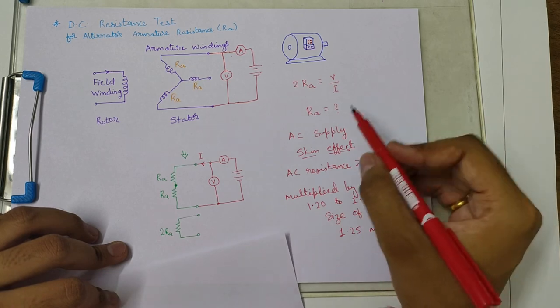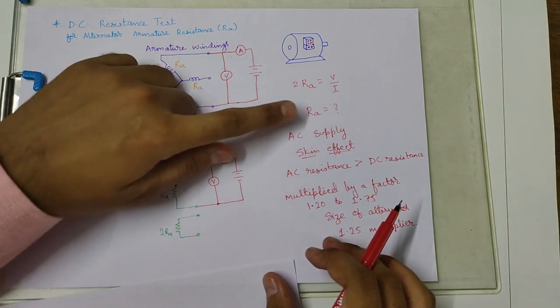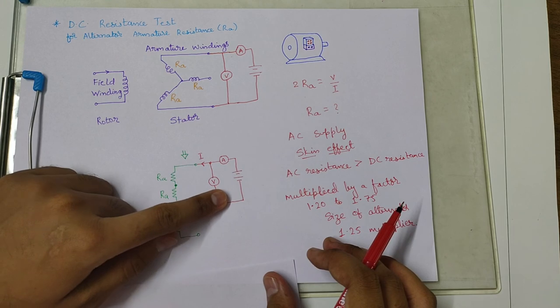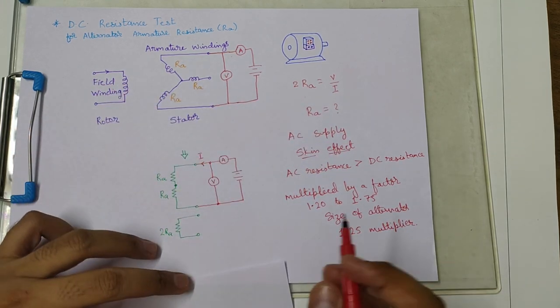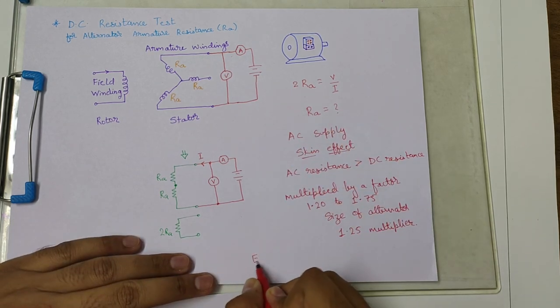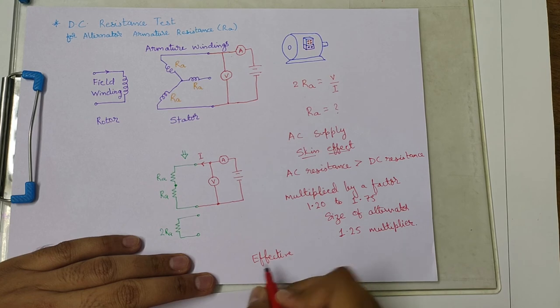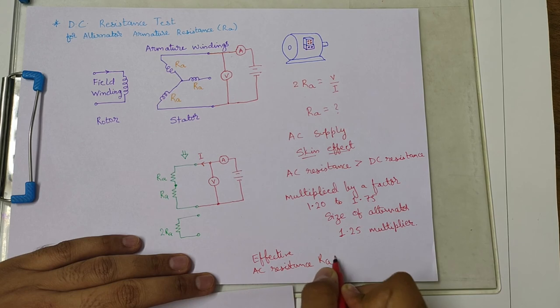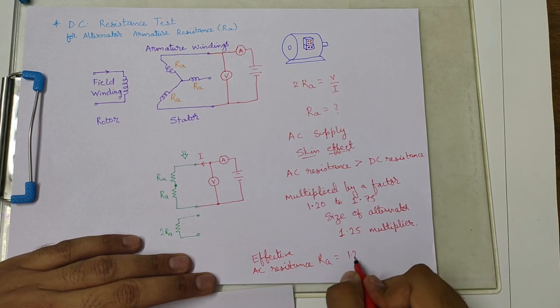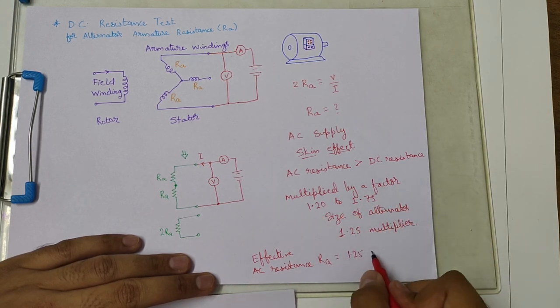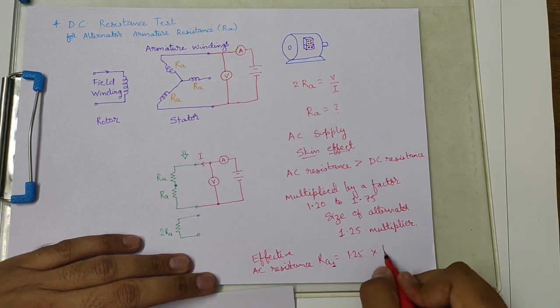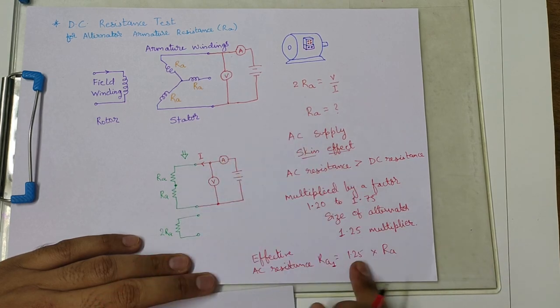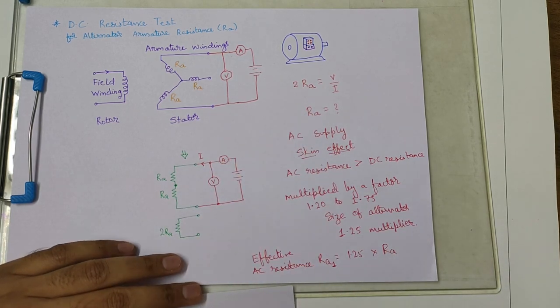To get the actual value of AC resistance, whatever value we are calculating by the method of supplying DC current is multiplied. So the effective AC resistance RA will be equal to 1.25, or depending on the size any multiplying factor, multiplied by the DC resistance RA. So this value will be multiplied by 1.25.